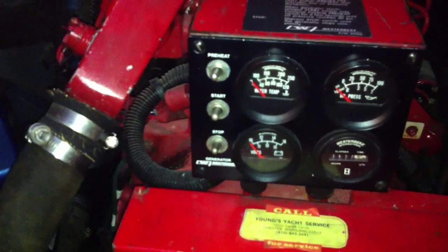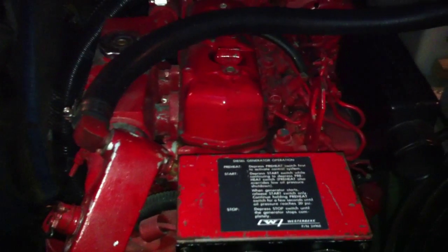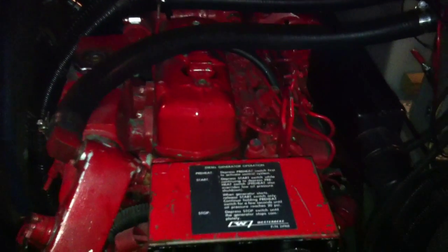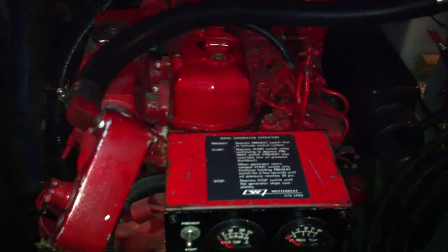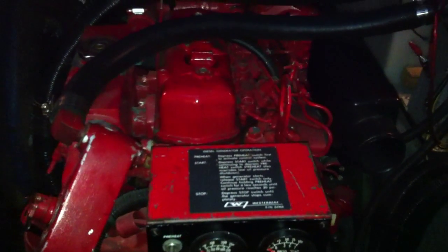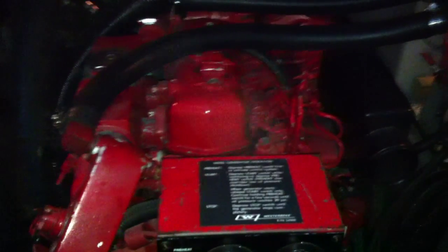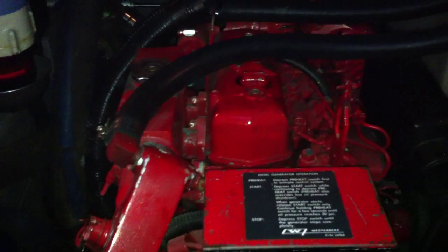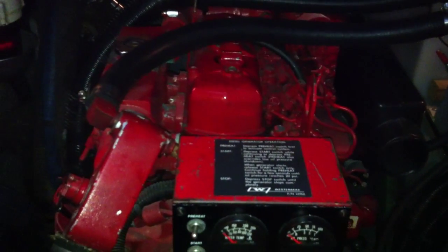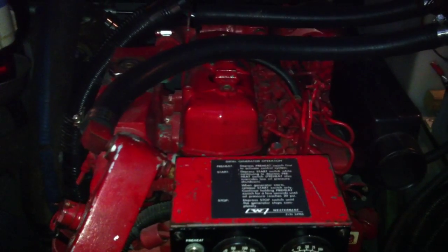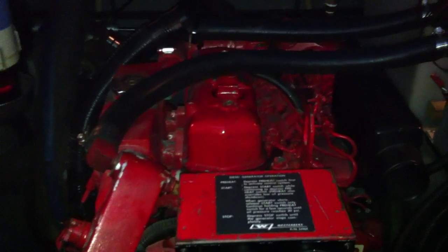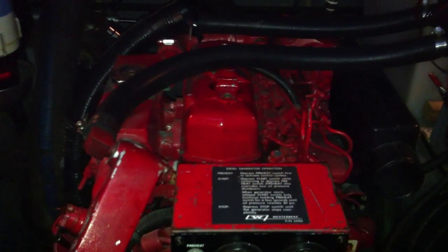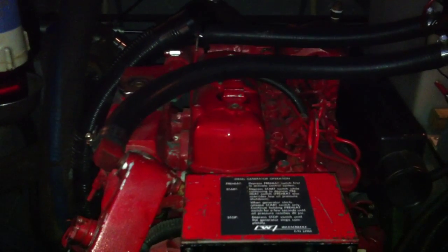Maybe just every couple seasons or so, run over the whole thing and tighten up anything you can get to, any wrenches, any bolts. I know some manufacturers tell you to torque the heads - I can't remember the exact interval, maybe 750 hours or so, but check your manuals. Other than that, it's the typical oil change, filter, and impeller - that's really the biggest thing with these. Maybe check your belt on your alternator, your coolant fluid level, and your oil level. There's also a metal air filter on this that you can take out, hose off, and clean, and that's really it. If you keep up with that, these things just run forever and give you incredible service.